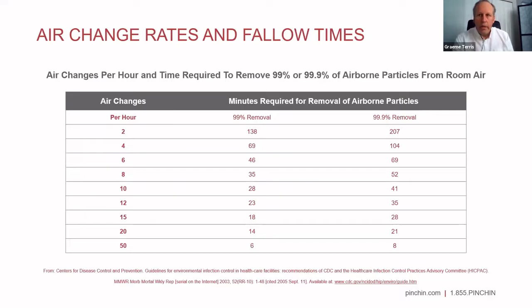Generally, your normal HVAC system will operate at around about 4 air changes an hour, which will give you a fallow time of around about 104 minutes, which is a long time. I think the document guides you to the fact that you might be able to utilize a portable air cleaner on top of that, which will increase your equivalent air change rate to getting on for the 20 to 30 air change range. If you add a portable air cleaner to your operatory, you'll get up to that sort of range, and the filtration will allow you that air change rate.